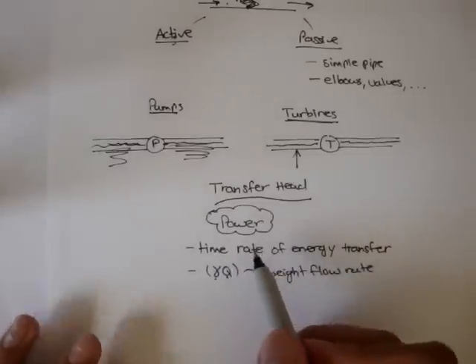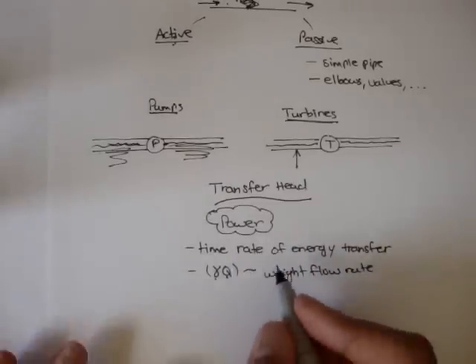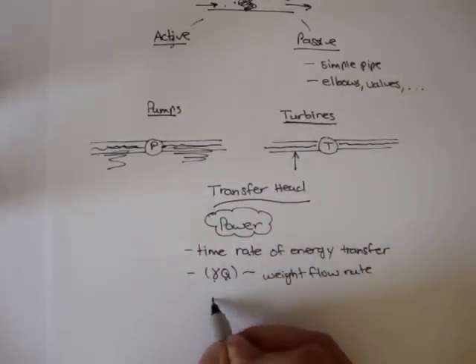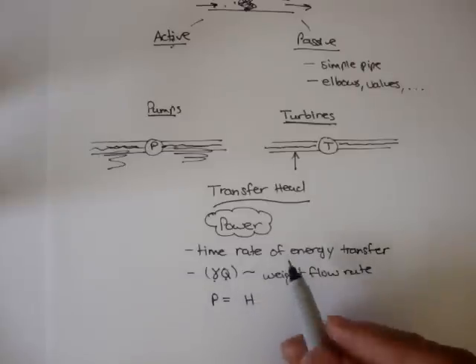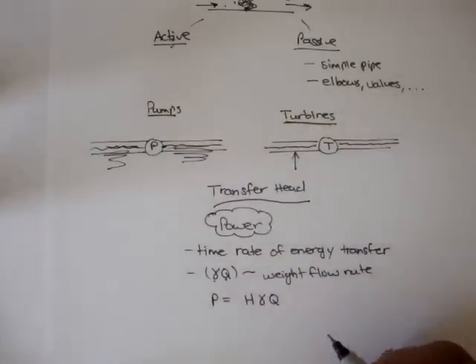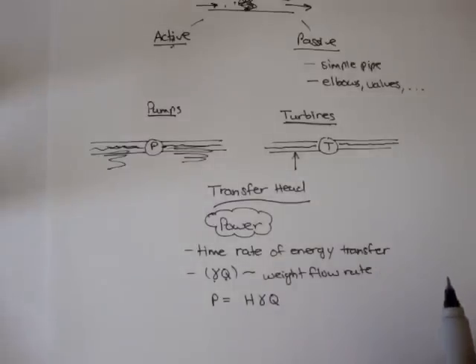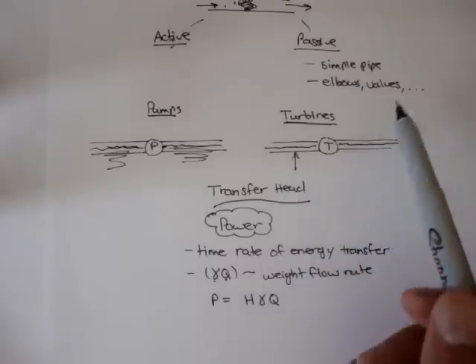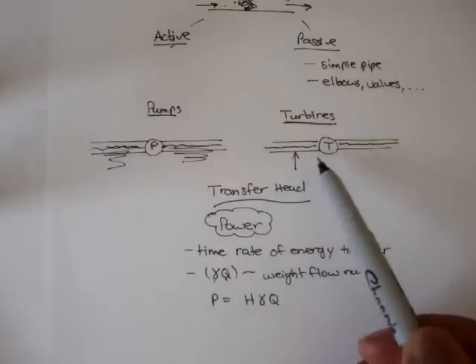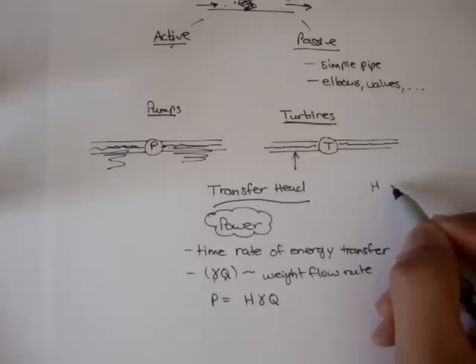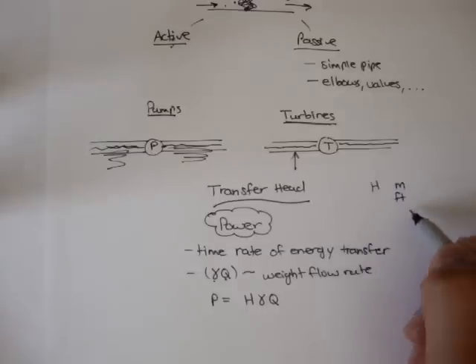Power is equal to the product of the device transfer head — either a pump or a turbine — times the weight flow rate. So we can say power equals the pump head or turbine head times gamma Q. Remember, the transfer heads represent the energy content — a turbine taking away energy or a pump giving energy to the water. Heads are usually in units of length: meters, feet, inches, centimeters, etc.